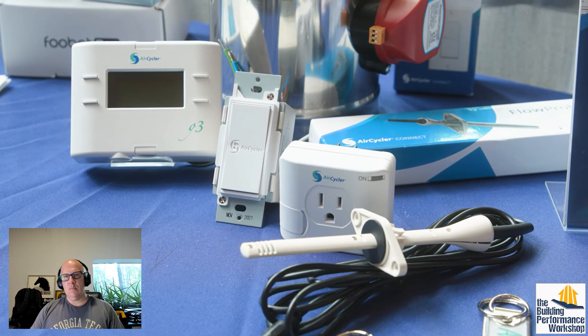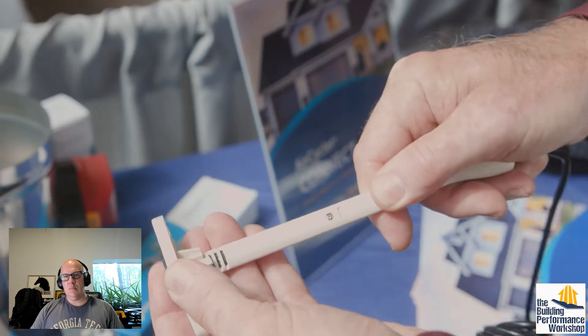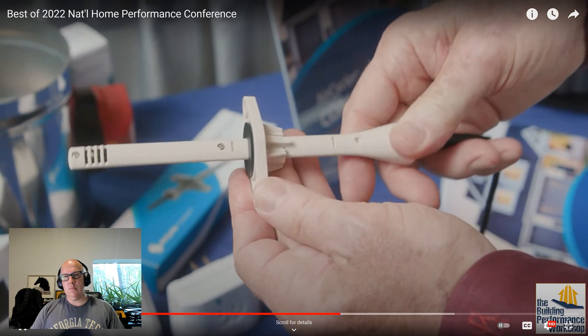There's also a temperature, humidity, and airflow probe — basically a hot wire anemometer. You can't immediately read the duct temperature because it may reflect the basement temperature, so the system lets it run for a couple of minutes to bring in outside air before taking a temperature reading, then starts measuring flow in CFM going into the air handler to ensure proper ventilation. The real beauty is: if that CFM starts to drop, the system can determine your filter is clogged. You can set a flow rate threshold in the app, below which you'll receive a text or email alert.